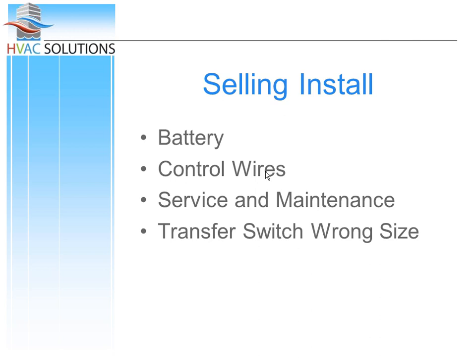Transfer switch being the wrong size - we size transfer switches based on the amount of amps coming to the house. So if you have 200 amp service coming to the house, we recommend a 200 amp transfer switch - service rated is probably about 90% of what we do, if not a little more. What happens if you have 200 amps coming to a house running through a 100 amp service rated transfer switch? It's going to get overloaded a lot, but best case scenario, you just cut down the delivered amps to that house to 100 amps. Power from the house actually runs through the transfer switch. I want you to understand that, because a lot of times people say, hey, I'm just using a 10 kW, why would I need a 200 amp switch? Well, because power from the house is running through it.